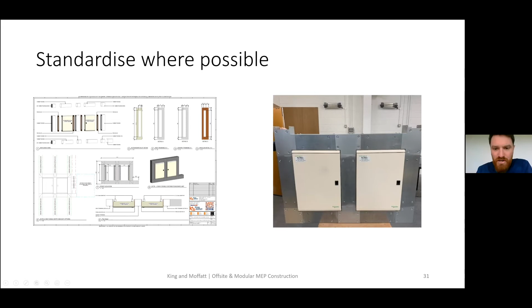This is what we've done with the brackets - we've come up with a naming convention for our brackets, and for all of our BIM modelers it means you can't really go wrong. The only ones we want manufactured off-site are the only ones people can choose from in our Revit template. We used to have to do very detailed drawings of the brackets in the past, but we don't have to do that anymore because it's all captured in our file naming - the type of uni strut, the length of it, the type of hanger, whether it be a gripple or a threaded rod, and what length it has to be, and what it's fixing onto.